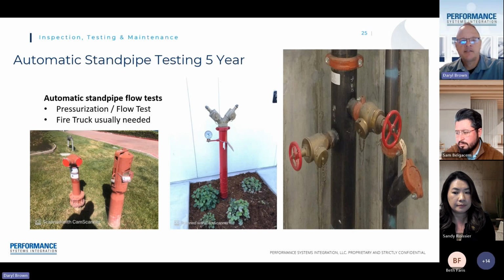Any standpipe system requires a certain amount of pressure to be able to supply the necessary water to hoses. So what we do every 5th year on these standpipe systems is we actually bring out a fire truck and we pressurize and flow water as the fire department would do it. So pretty much we're testing this standpipe every 5 years, besides the annual inspection and quarterly. Every 5th year, we're going to test it like the fire department will use it. So we're going to pressurize it and flow water.